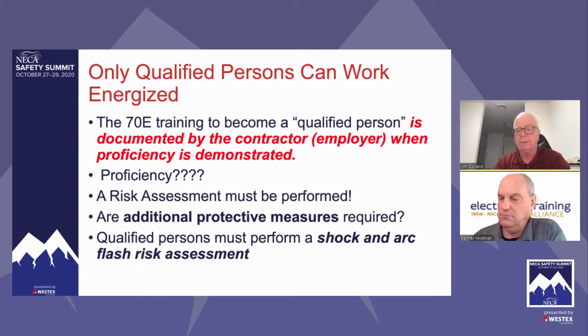And as a safety coordinator for IBEW Local 98, I had the responsibility to investigate every incident. And where there were incidents, I can tell you in every single case, the owner of the facility was there and said, we don't know why they didn't shut it off. We don't know why, because to them, it's just shutting it off. Palmer and I, and you should know that it's much, much more than that. We can't just open a disconnect. But what ends up happening is that the owners, after an incident will say, we don't know why they didn't shut it off. That's why if we run into an owner and the owner says, no, you got to do it energized, you fill out that energized electrical work permit and you give it to them to sign. All right. You make sure that they've got skin in the game. They are responsible for their equipment if something goes wrong.